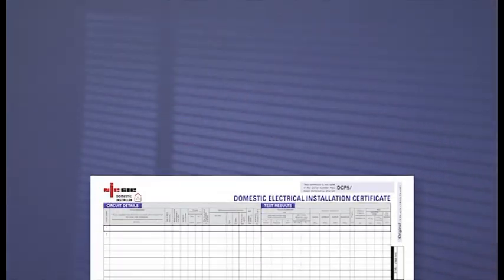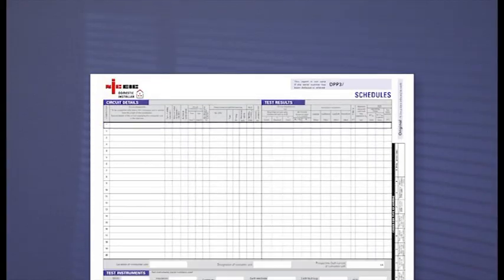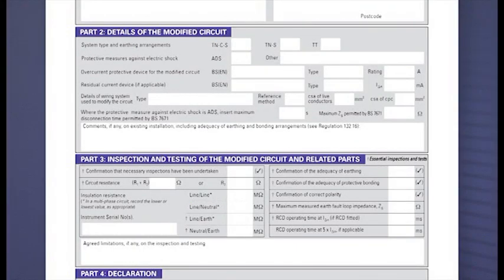The circuit details and test results take up a full page on both the EIC and EICR, whereas the minor work certificate only deals with information for a single circuit and so has an abridged version. So the first issue I'd like to tackle, Tony, is how this should be filled in to best represent the installation you're working on. Now, for example, it's common to have a split load consumer unit with 2 batches of RCD protected circuits. So what's the best way to show this on paper?